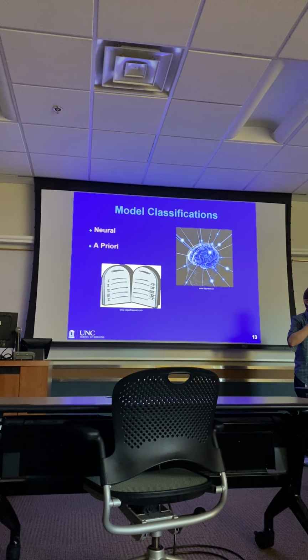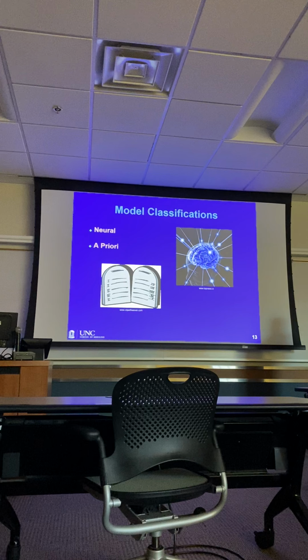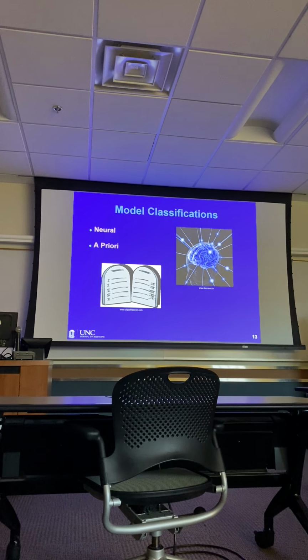It's learning, okay, this is what a histogram should look like for a chest. This is what a histogram should look like for a knee. So the system is learning what your typical exposure patterns are and generating a model histogram, so that when you make an exposure, it's got something to compare it to.